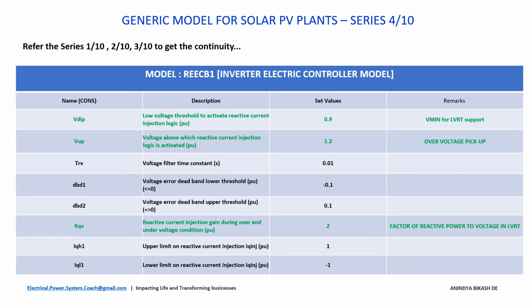Similarly, VUP, voltage above which reactive current injection logic is activated, that is the over voltage limit. So in any grid code, if it is specified as 1.2 or 1.3 per unit, in this case I have specified as 1.2 based on one certain grid code. This is the over voltage pickup. So beyond this point, if the voltage at the POC increases above 1.2, and at the same time the terminal voltage at the inverter increases above 1.2, in that case the inverter will go to HVRT mode, that is high voltage ride through mode. Okay.